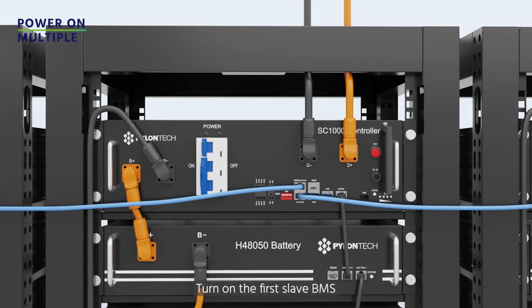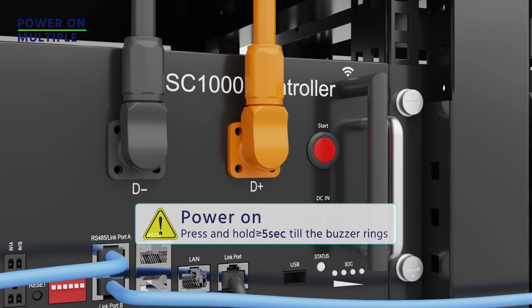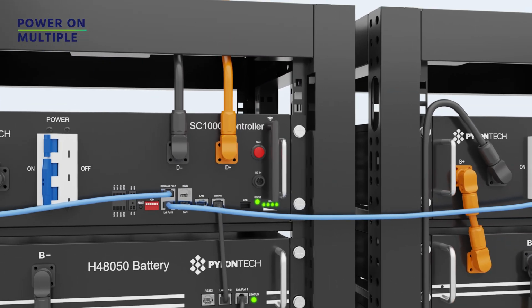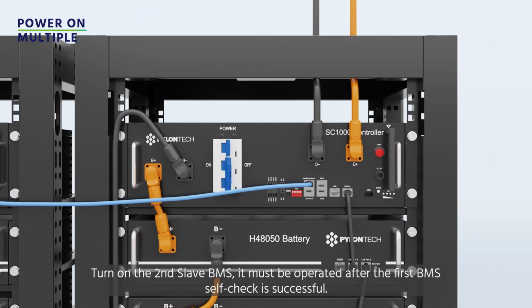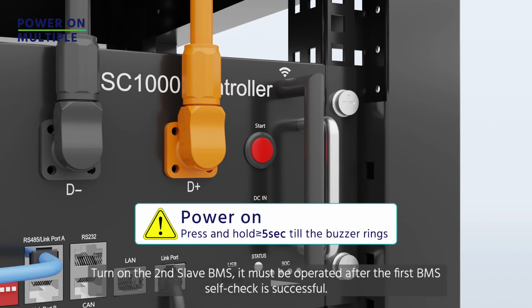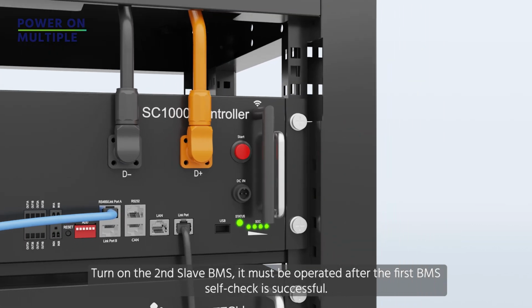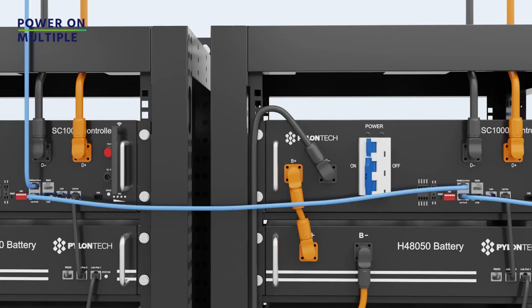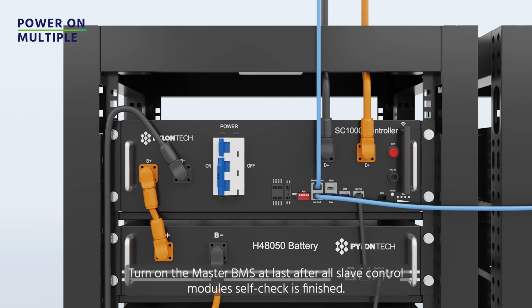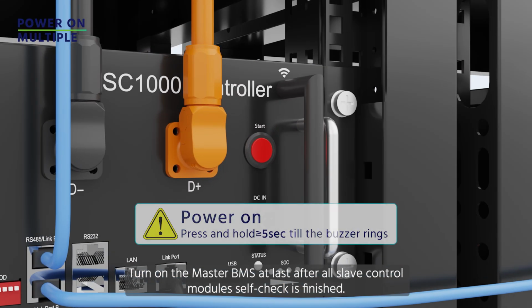Turn on the first slave BMS. Turn on the second slave BMS. It must be operated after the first BMS self-check is successful. Turn on the master BMS last, after all slave control module self-checks are finished.